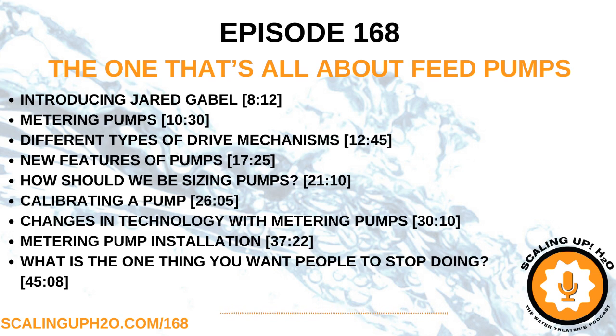What's the one thing that you see people doing that you just want them to stop doing? I have to laugh at this, because it's maybe more of a pet peeve of mine, but I know that it's very common to just power pumps on and power pumps off. I get it. But the pumps have, these days, the ability to take signals. There's a lot of signals that we send from PLCs, like I said earlier, a 4 to 20 milliamp signal, and you can basically stop the pump by sending it 0 or 4 milliamps. But in most pumps nowadays, you can also give it a discrete contact closure to start or remotely stop the pump. All I would say is let's take advantage of that technology, where you can just use a simple relay to start and stop the pump with a command.